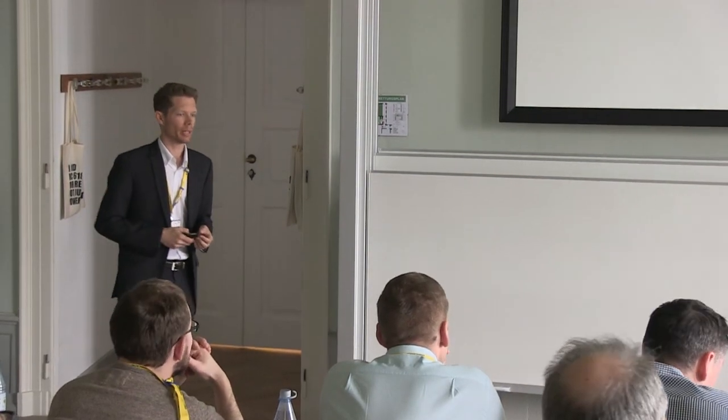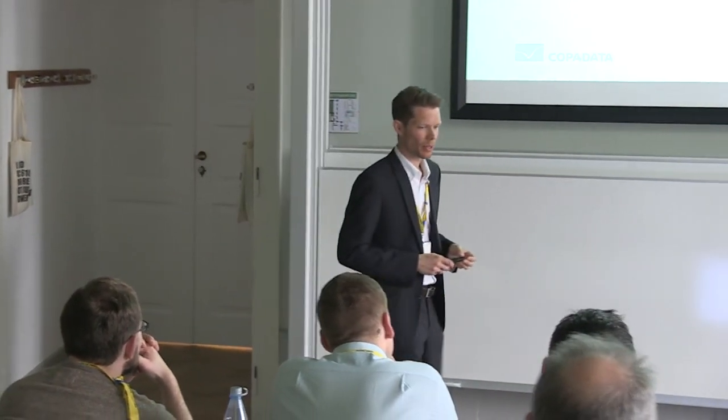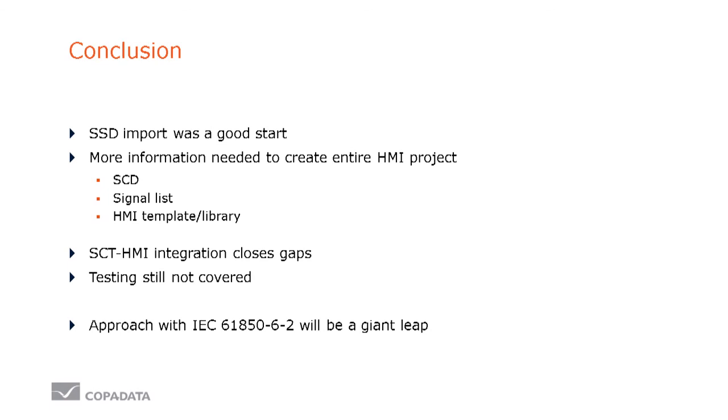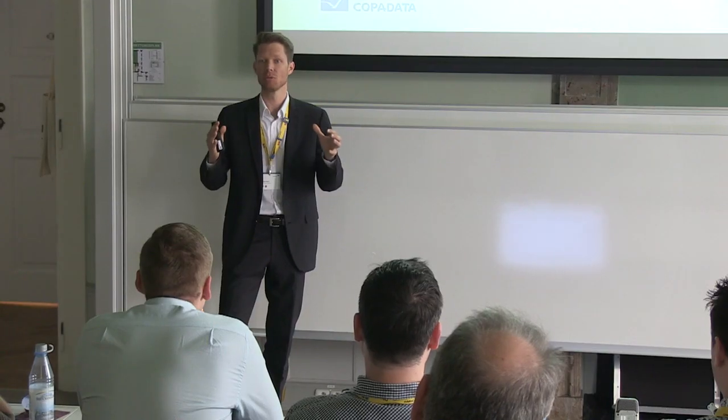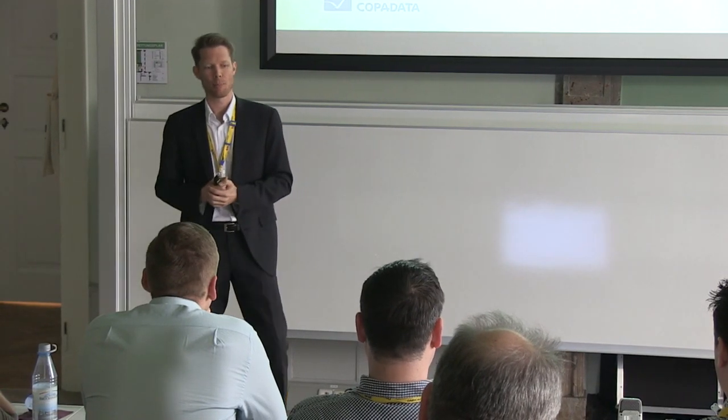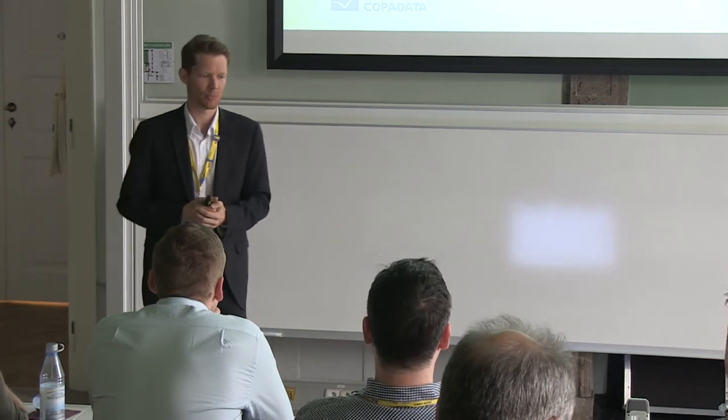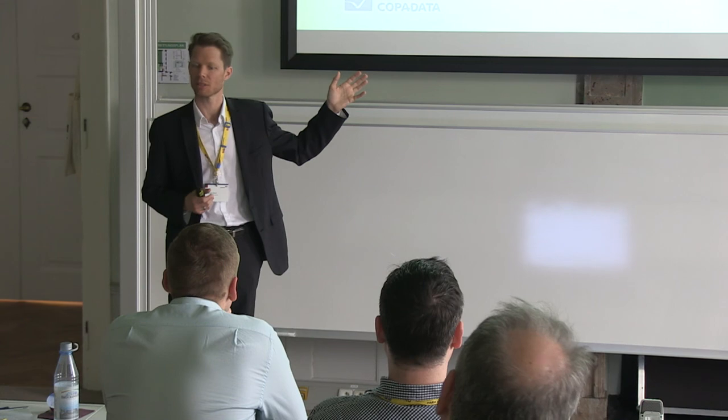And now I would like to conclude and summarize. The SSD was an important start, thanks to Jörg. More information is needed than what is available in the SSD. So we need the SCD file, we need a signal list, we need HMI templates or libraries. The integration of an SCT and the HMI would definitely close some gaps. So if you can run these two tools together, it has significant advantages. But as I said, testing is still not covered here.